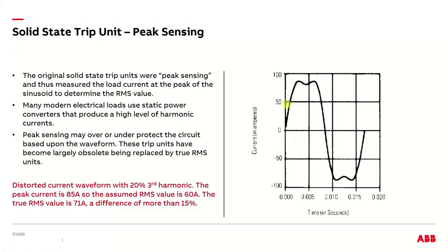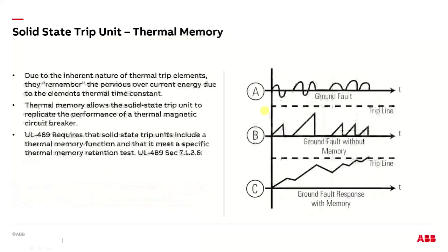That's a historical artifact because nobody makes them anymore, but you will see them in the field, and it can be a problem. So if you have some strange tripping activity on a breaker that serves a harmonic load, you may want to look into it and see what type of breaker it is, because you may have run into this problem. It's still out there. The last component, and the important one, is thermal memory.